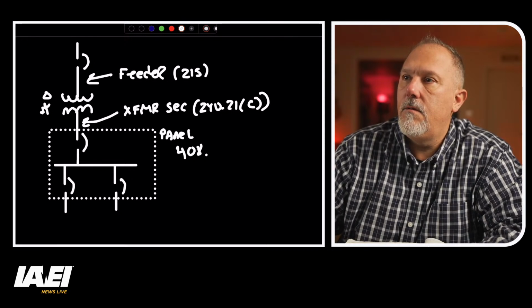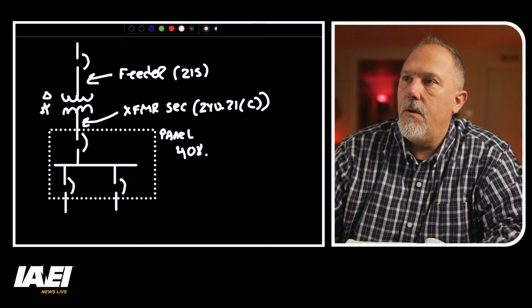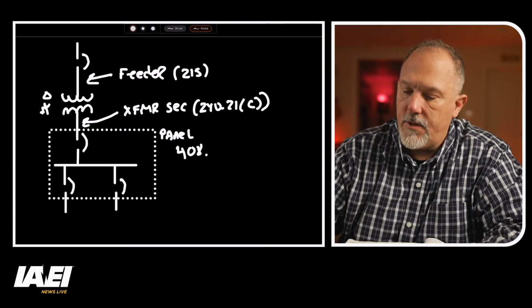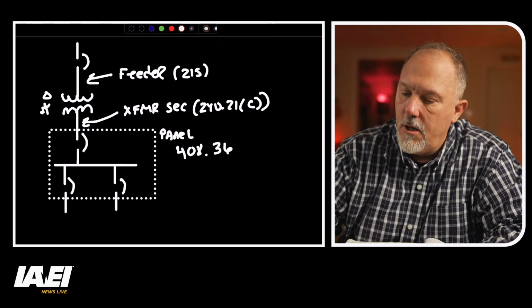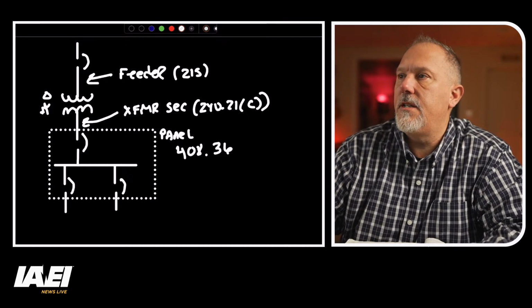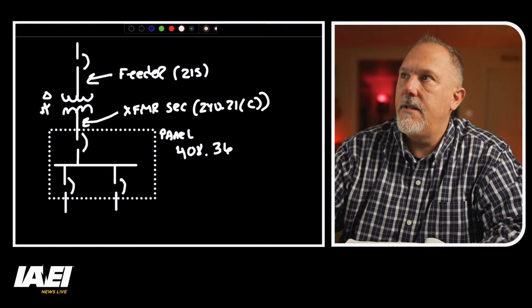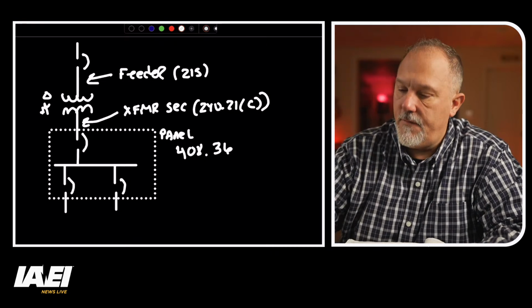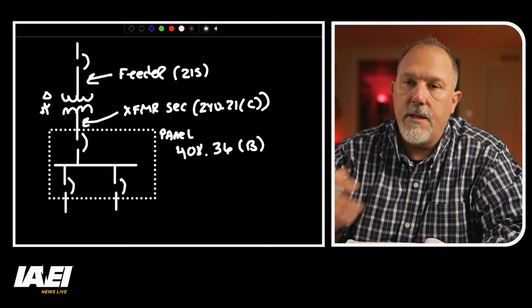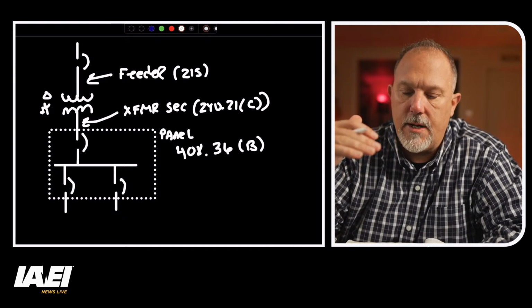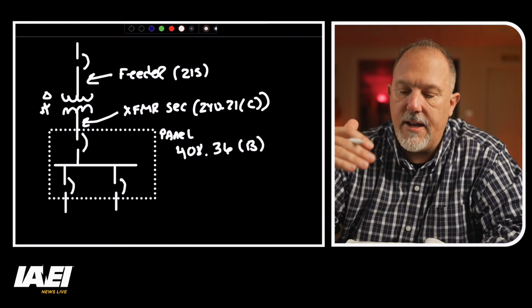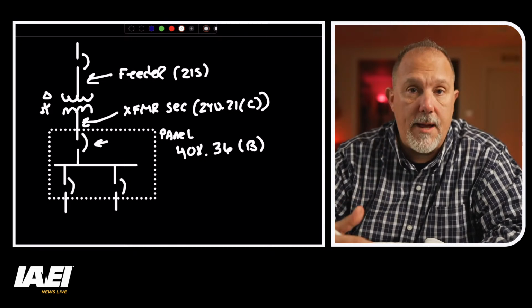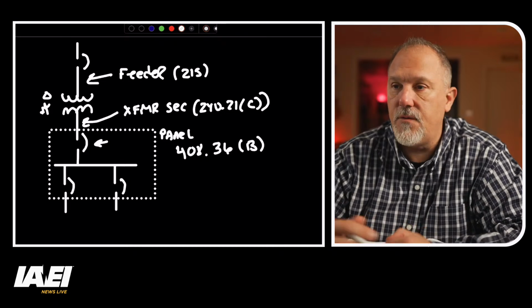And this would be 408. I know we're getting a little beyond 408. I have to go to panel boards, which is Part 3, 408.36. 408.36 is going to tell me that, in fact, 408.36(B) is going to tell me that for a panel board supplied on the secondary of a transformer, you have to have the overcurrent protective device for that panel board located on the secondary of the transformer.